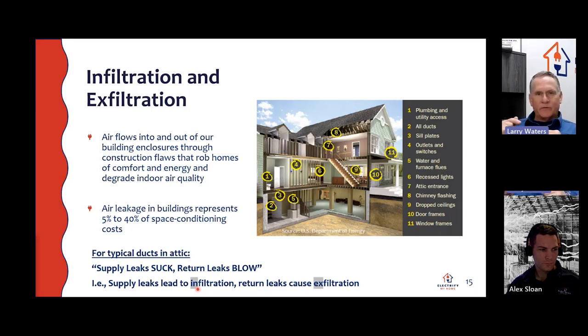If we have a very low differential and our ducts are tight and our return air is sealed well, we should not have infiltration and exfiltration dramatically that's caused by the ductwork. So that's something that's really important to understand: supply leaks cause the house to infiltrate. Return leaks cause the house to exfiltrate.